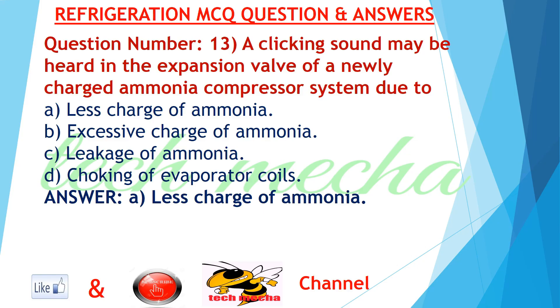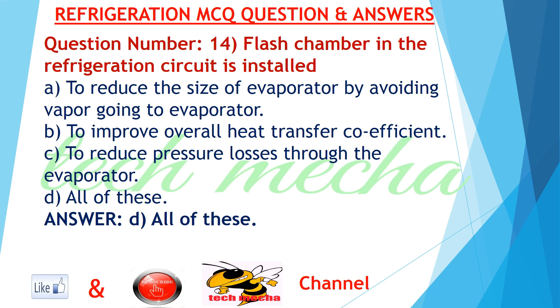Question number 13: A clicking sound may be heard in the expansion valve of a newly charged ammonia compressor system due to A. less charge of ammonia, B. excessive charge of ammonia, C. leakage of ammonia, D. choking of evaporator coils. Answer: A. less charge of ammonia.